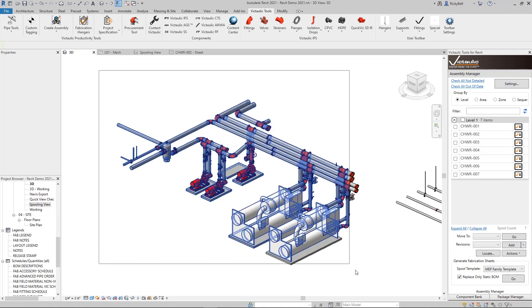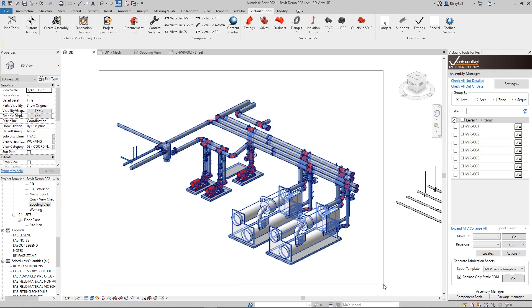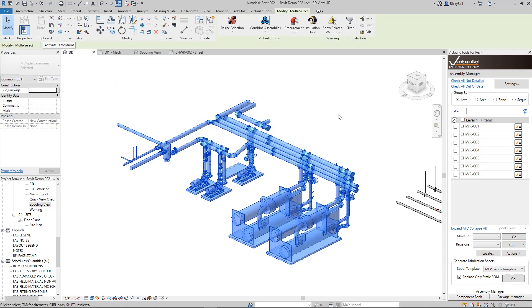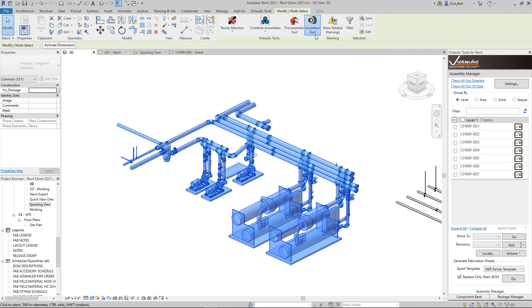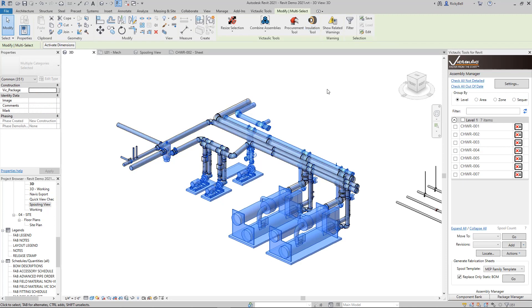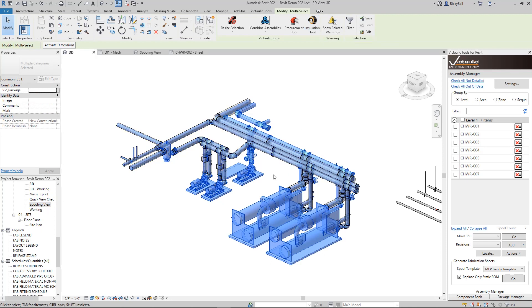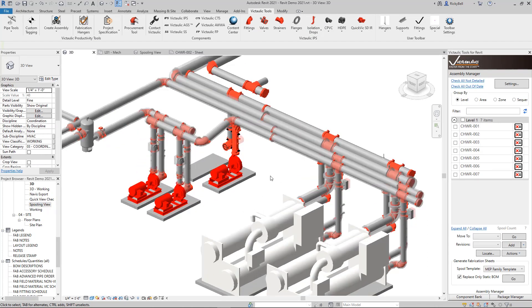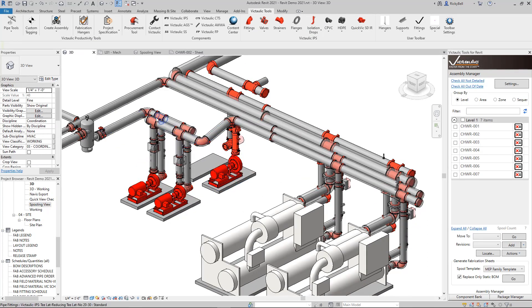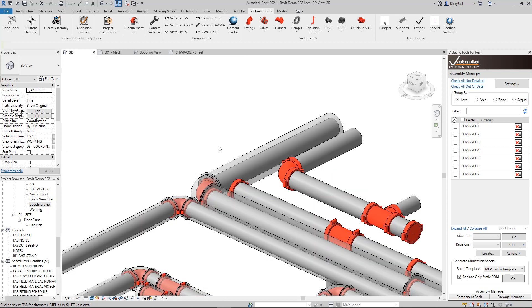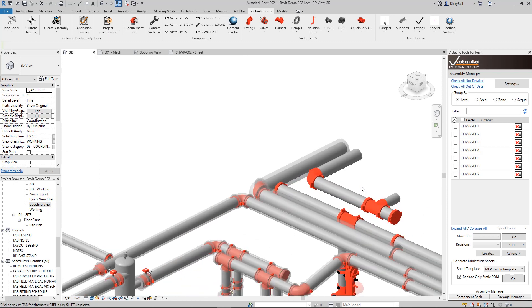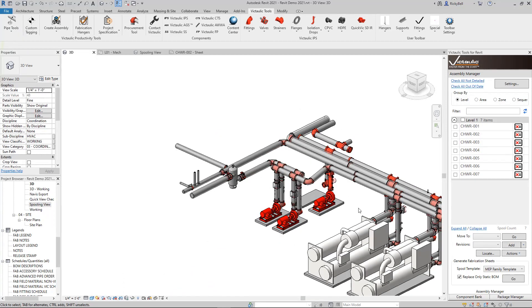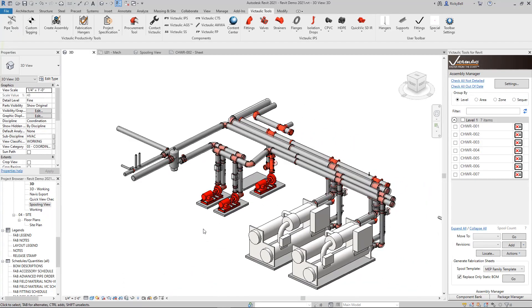So now with my project spec set up correctly, all I really have to do is make a large selection and click on the installation tool up in the Victaulic Tools ribbon. Here are our results. After the tool is run, we can see that an inch and a half of insulation goes on to our chilled water supply and return. Three inches of insulation gets applied to our condenser water return, and then no insulation is put on our condenser water supply, and that's what we wanted.